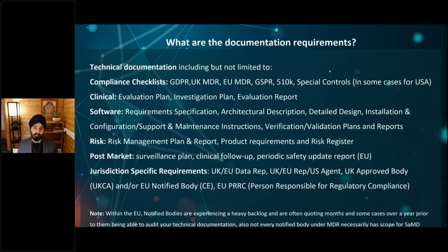Also, a very, very important factor that people don't realize is that at this current moment in time, when the EU transitioned from the old medical device directive to the new MDR, we lost quite a number of notified bodies. So there are now fewer people that can certify you. To make matters worse, every notified body has something known as a scope. Not every notified body has the resources or the required expertise to be able to regulate a medical device. Hence, that scope drops even further. In my experience, I have seen notified bodies now quoting over a year before they're able to even look at your technical file.